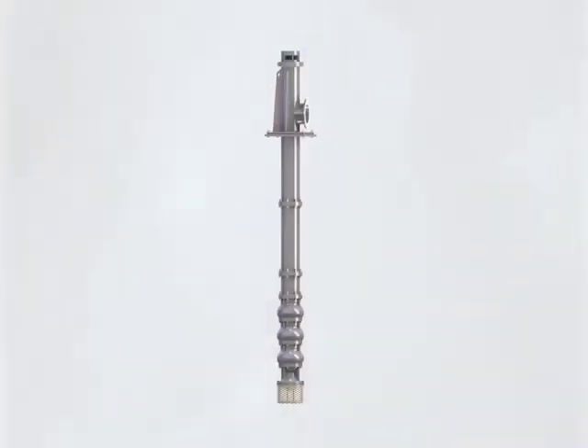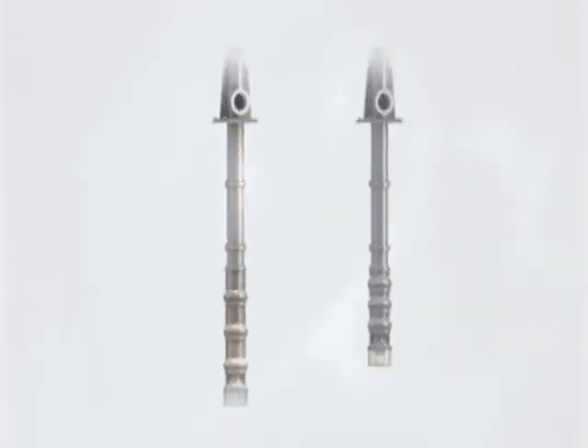Rebowling, on the other hand, entails replacing the liquid end of the pump and requires less than 2 days of downtime. In this case, the pump is temporarily shut down to take a few key measurements and quickly return to service while a new bowl assembly is ordered. Once it arrives, it takes less than 2 days to install the new bowl assembly and return the pump to service.